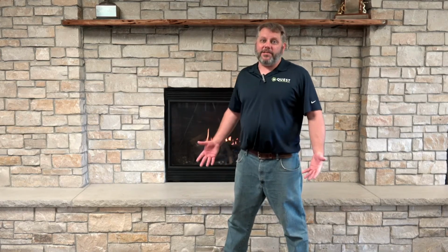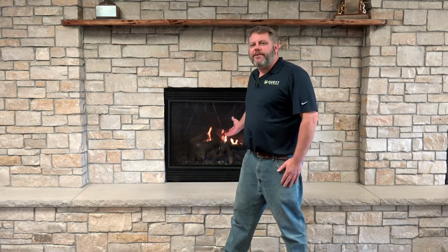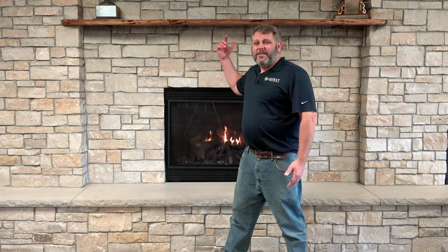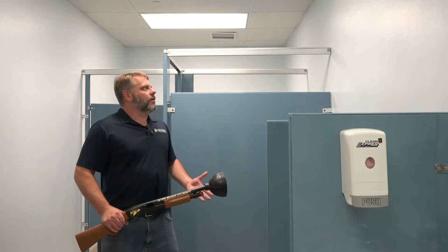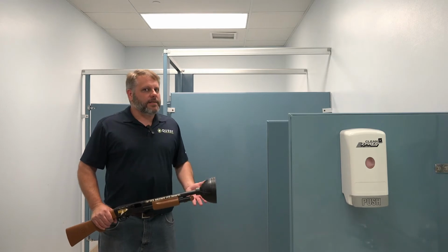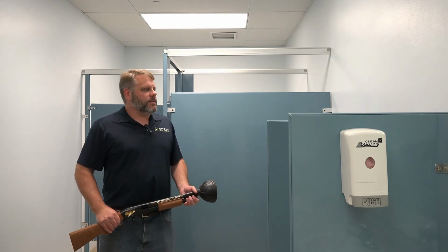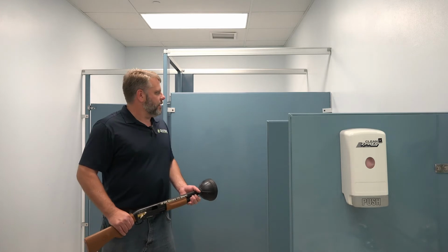That outside air also has to make up for the air taken out of the building by combustion sources, such as furnaces, boilers, water heaters, or even your fireplace. Anytime we're drawing air in for the combustion process, air's going up and out the chimney, and that's got to come from someplace. And when it comes in, we're bringing in moisture. We also get a lot of moisture in the building from makeup air for things like exhaust fans, or the bathroom, where exhaust is very necessary to get rid of moisture and other smelly things out of the building.